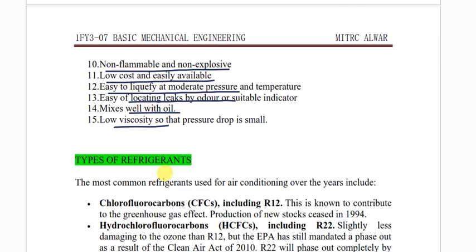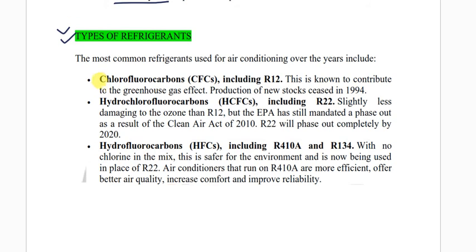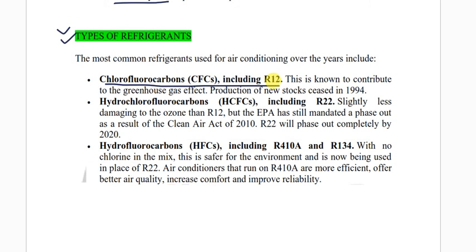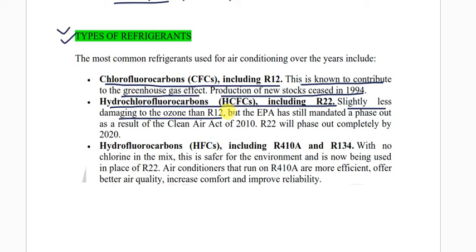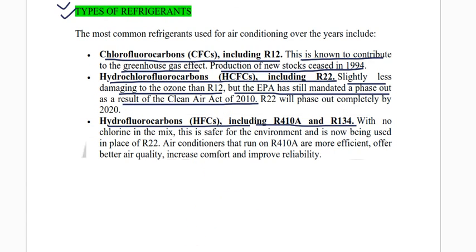These are the properties of refrigerants. Types of refrigerants include: Chlorofluorocarbon R12, which contributes to the greenhouse gas effect and whose production of new stocks ceased in 1994. Hydrochlorofluorocarbon (HCFC) including R22, which is slightly less damaging to the ozone than R12, but the EPA mandated a phase-out under the Clean Air Act of 2010. Hydrofluorocarbons (HFCs) including R410A and R134a are among the refrigerants currently utilized.